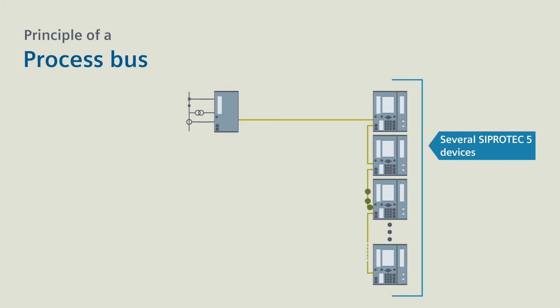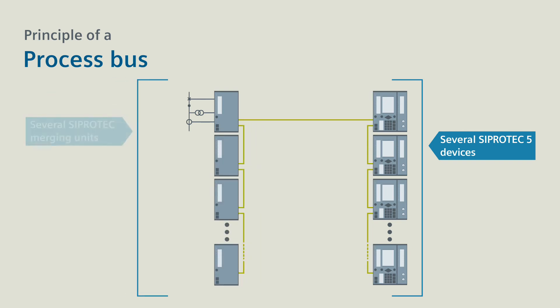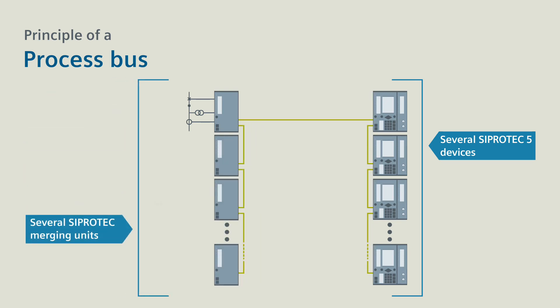Communication also works in the opposite direction. The SIPROTEC merging unit then outputs commands to the switching devices. You can connect further SIPROTEC merging units to the process bus, for example, for non-conventional instrument transformers in air-insulated and gas-insulated high-voltage switchgear.